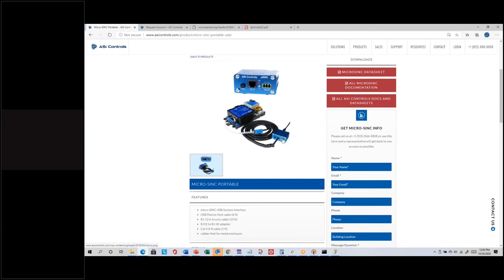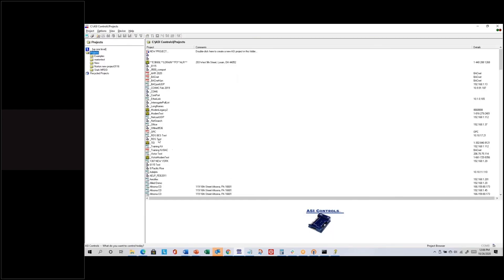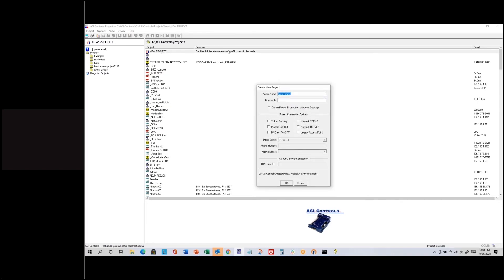For the ASI protocol RS-485 network, there's also a green plug where you can connect a communication wire directly to the Micro-SINC for testing on the RS-485 network itself. I have a Micro-SINC here — plugging USB into it, with a curly cable plugged into my VAV controller. In ASI Expert, I'm going to get out of this BACnet project to talk locally through the Micro-SINC. I'll click Project Browser — the third toolbar icon from the left — and create a new project by double-clicking New Project.